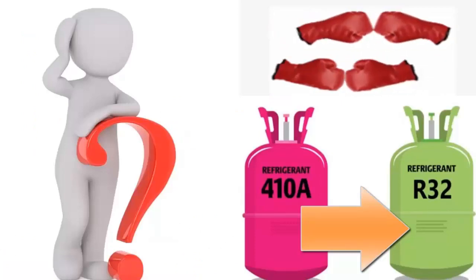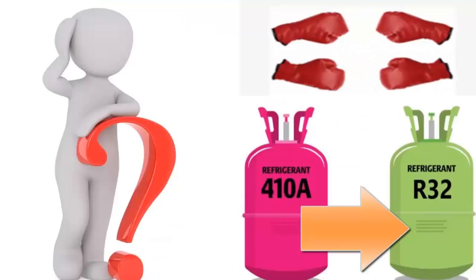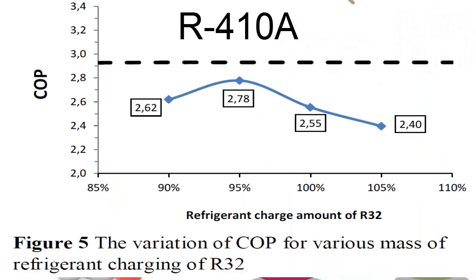10. The illustration shows the relationship between the coefficient of performance, or COP, and the charge of four different quantities of R-32. You'll notice that the COPs of these charges are lower than those of the standard system, indicating that a direct replacement of R-410A with R-32 will not raise the COP.